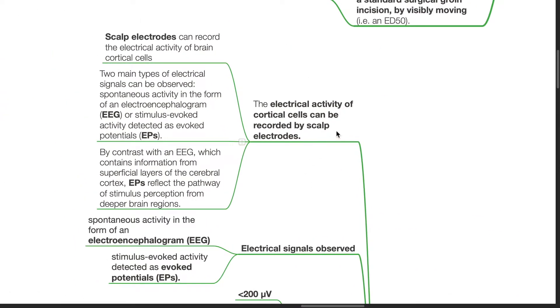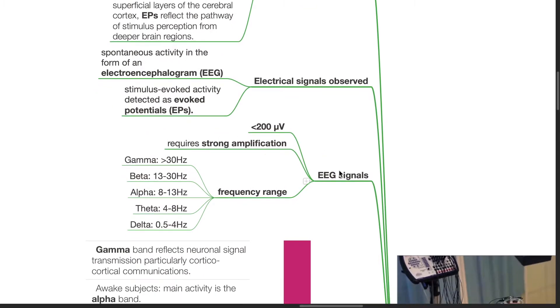We can monitor depth of anesthesia by brain function monitoring, which includes EEG and processed EEG. The electrical activity of cortical cells can be recorded by scalp electrodes, used to assess EEG or evoked potentials (EP). By contrast with an EEG, which contains information from superficial layers of the cerebral cortex, evoked potentials reflect the pathway of stimulus perception from deeper brain regions. The electroencephalogram measures the spontaneous activity of cortical cells, while stimulus-evoked activity is detected as evoked potentials. EEG signals are less than 200 µV in amplitude, thus requiring strong amplification.